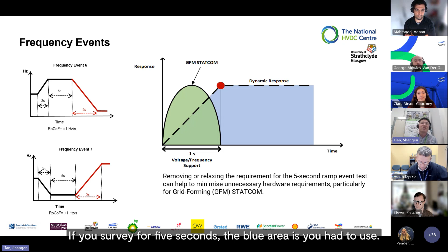If we ask the grid-forming STATCOM to provide voltage and frequency support for 1 second, the green area is the energy you need. If it supports for 5 seconds, the blue area is what you'd have to use. So we can ask the grid-forming STATCOM to provide inertia only up to the red dot.